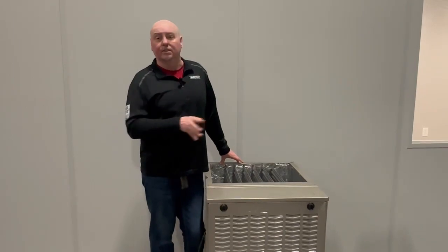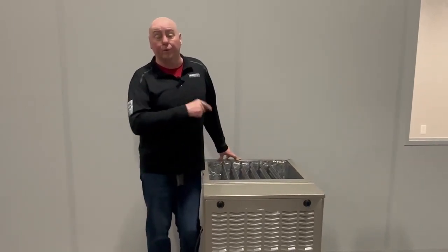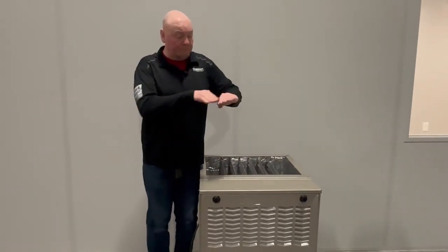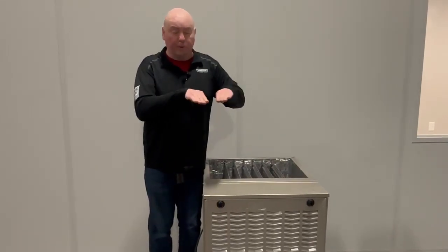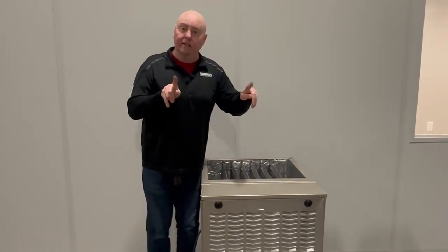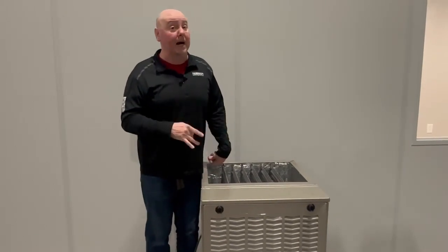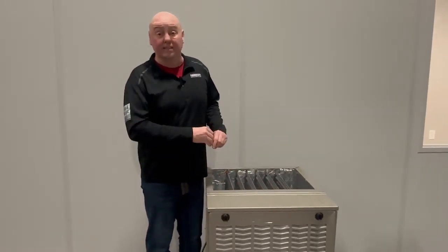So my best advice is to check the tabs against the heat exchanger before you install it. It's not the tabs on the back that get you in trouble, because they're supported by the bracket. It's the ones on the end that can lift up and down, and they snap and pop really loud if they get up against that heat exchanger.